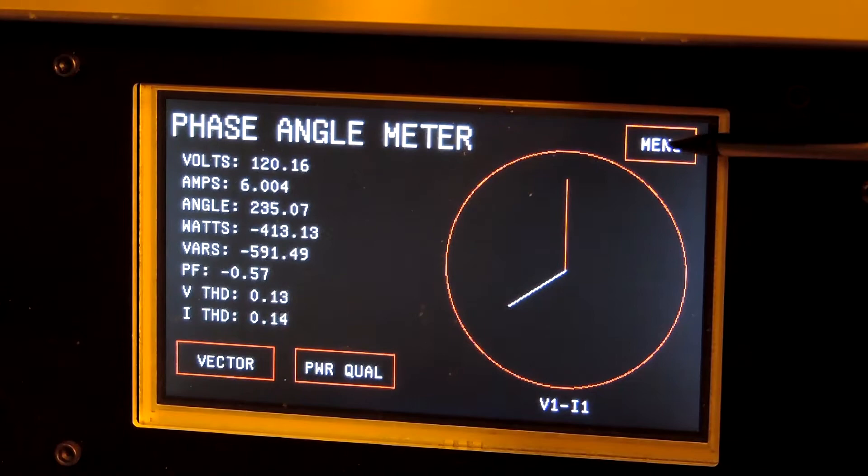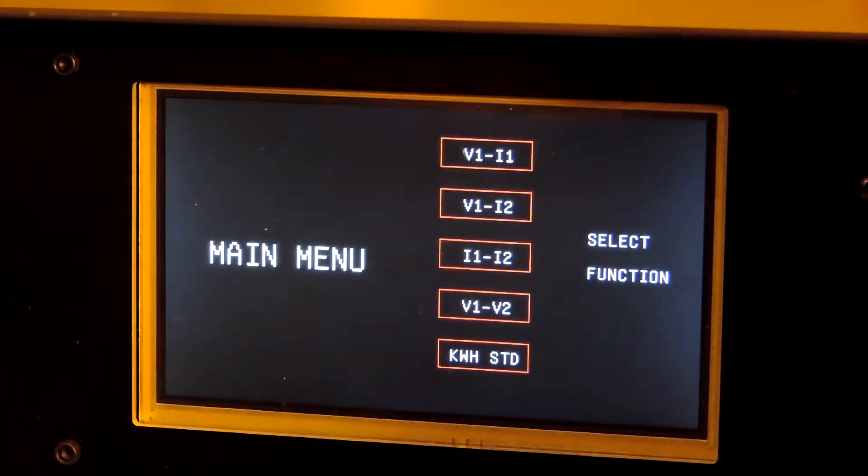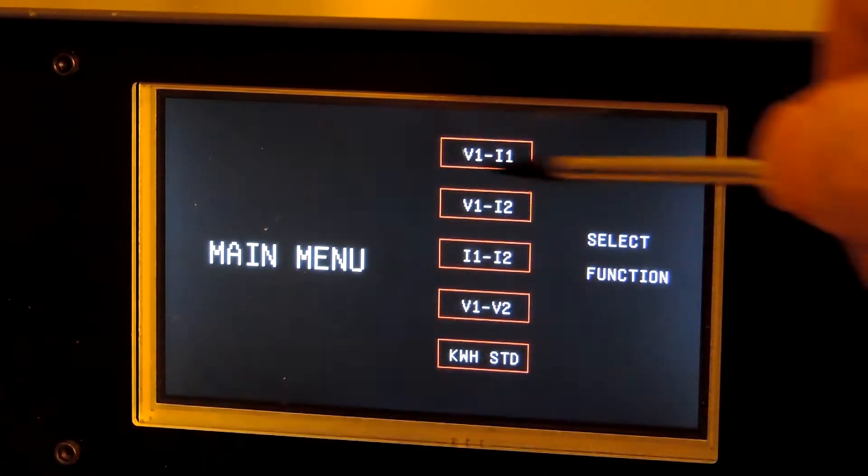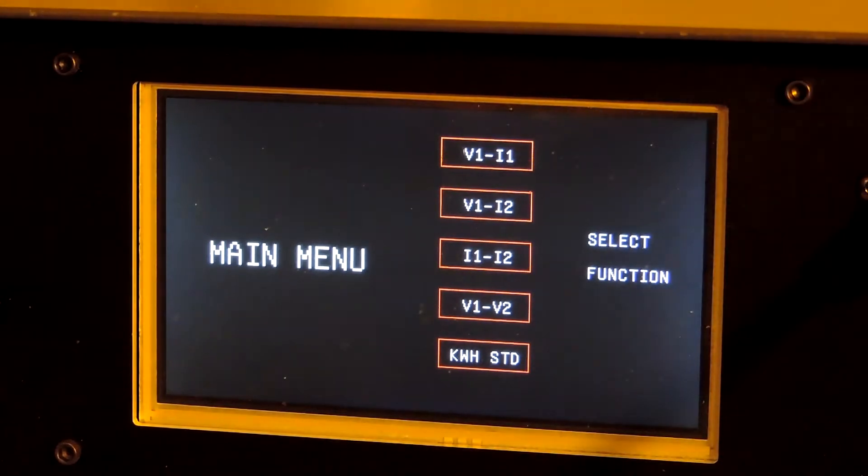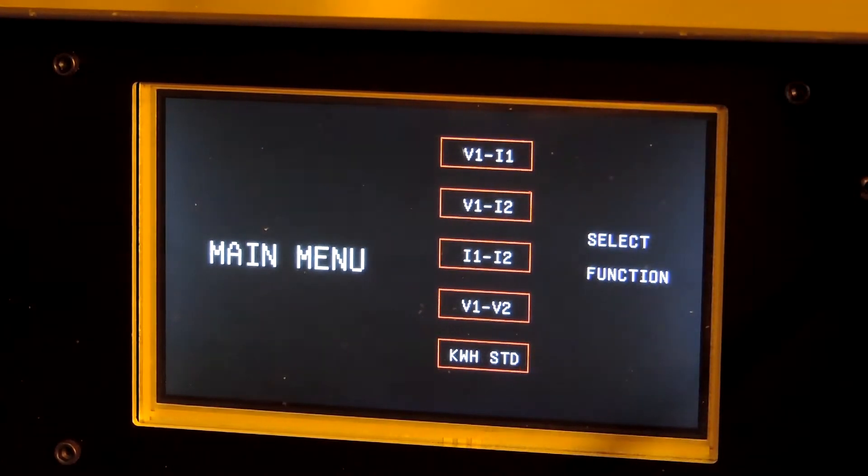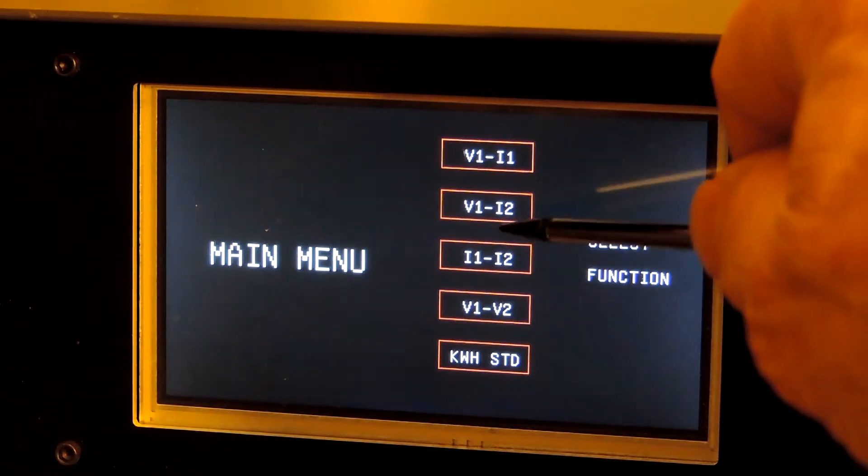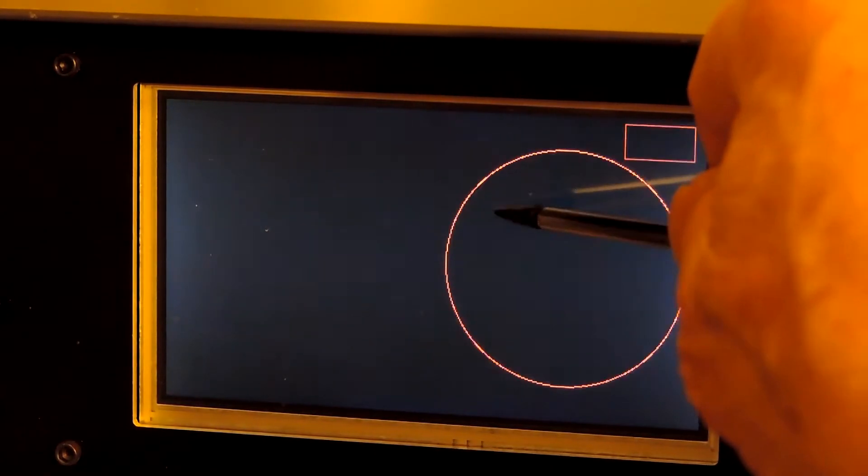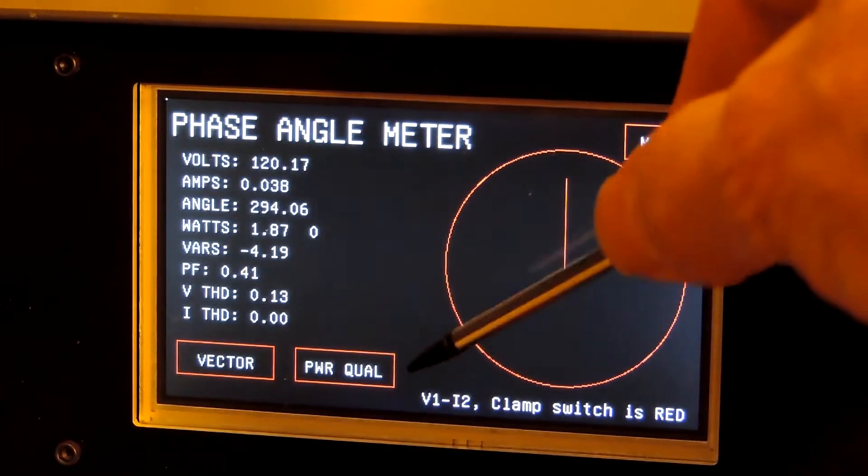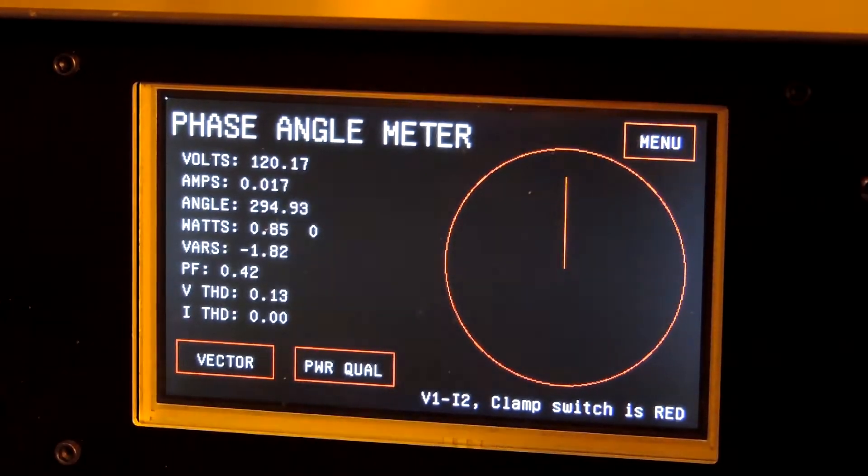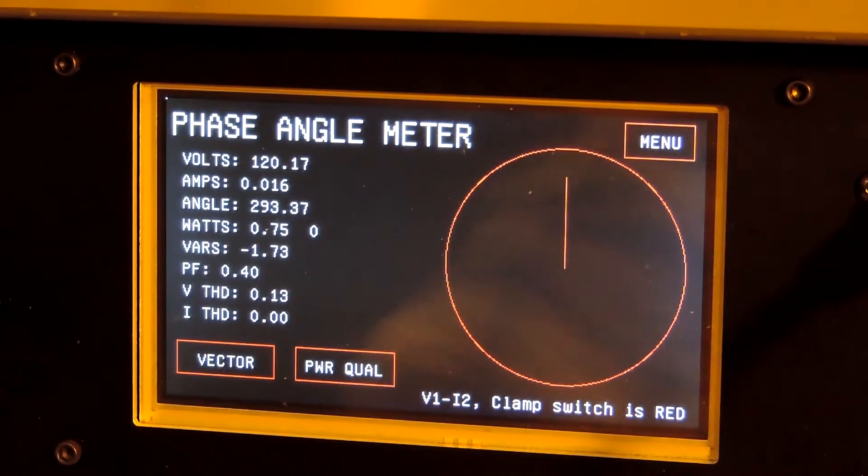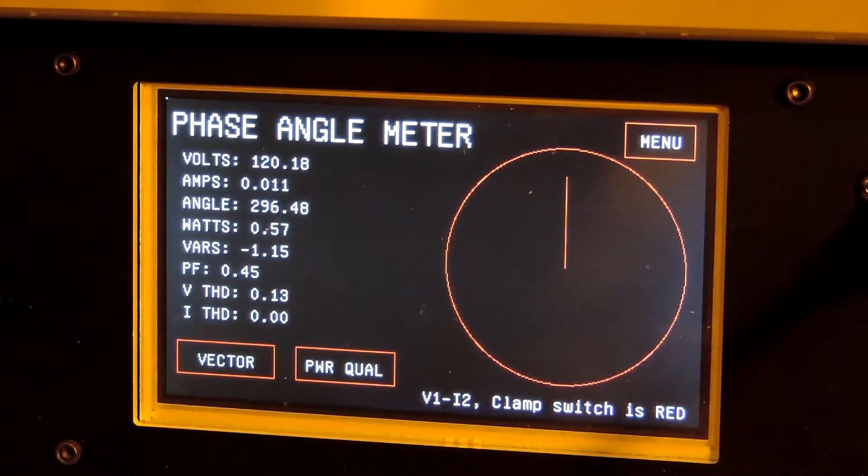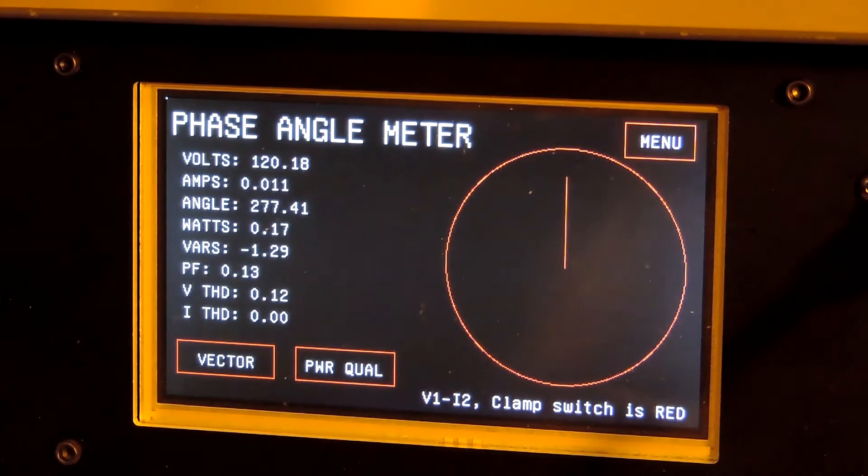Now it will also, go back to the menu here, it will also do a clamp-on as a clamp-on input. That's in case you need to use a clamp-on, you don't have a test switch or you want to compare two currents. So I'll go to V1-I2. It says down here clamp switch is red, so that tells you which way to face the clamp-on for that mode to get the angle right.